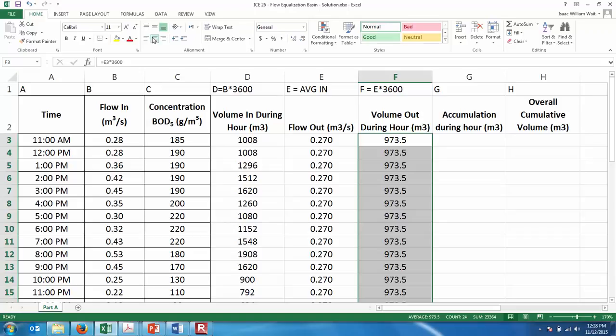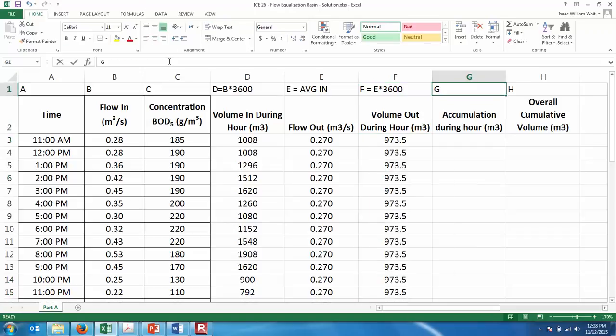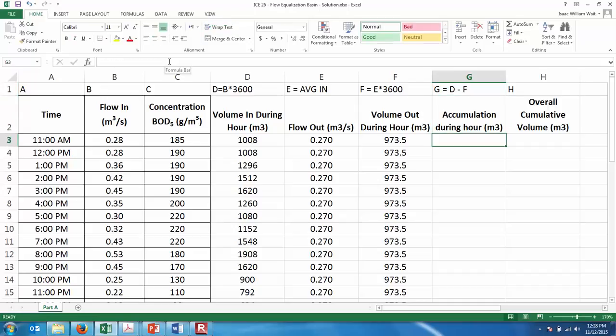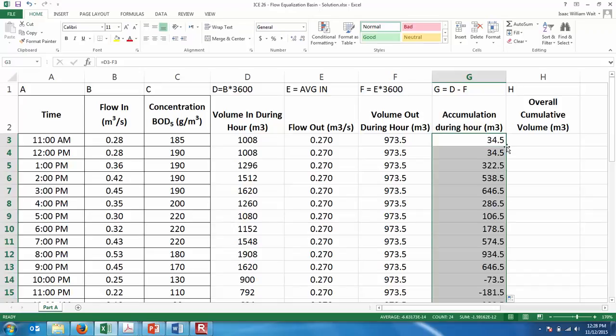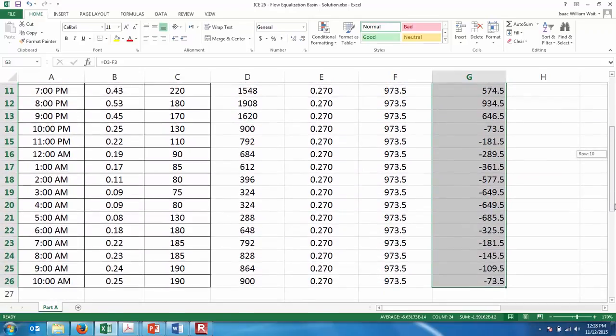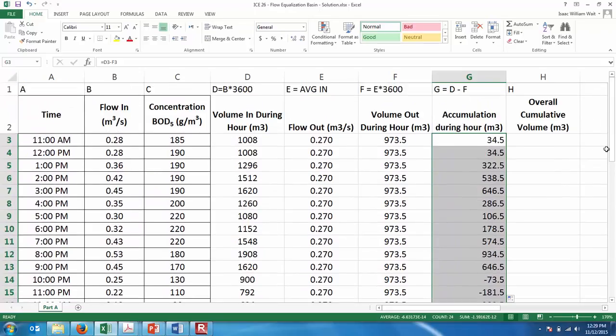Column G: Accumulation During Hour. It's going to be in minus out — D minus F. Equals Volume In minus Volume Out. In the first hour there's 34.5 cubic meters of water going in more than we're allowing to flow out, and that gets stored inside the tank. Double-click and it calculates for every hour the difference between in and out. In the middle of the night, instead of having a really low flow rate going to the treatment plant, we'll use the water from this tank so that we have a steady flow always going to the treatment plant.